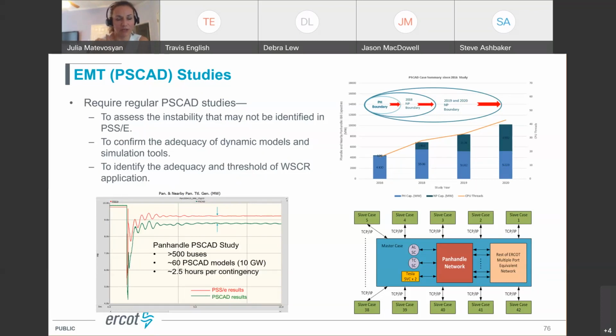Andrew Isaacs had a really good talk yesterday in the NERC IRPWG meeting, talking just about that. And this is just an example from a recent 2020 Panhandle PSCAD study showing that for an area of about 500 buses, we had 60 PSCAD models to represent this 10 gigawatts of inverter-based resources in and nearby Panhandle. And it takes about 2.5 hours to simulate just one contingency, even though we use parallel processing to speed up calculation.